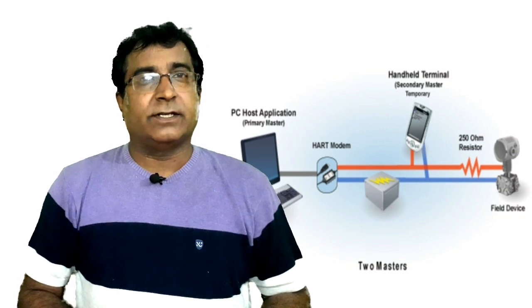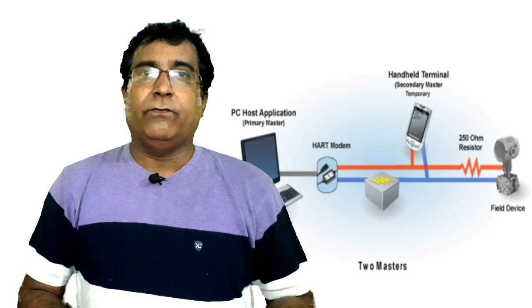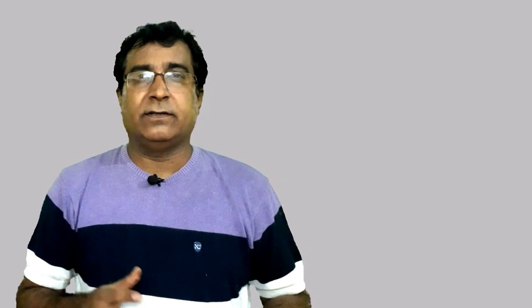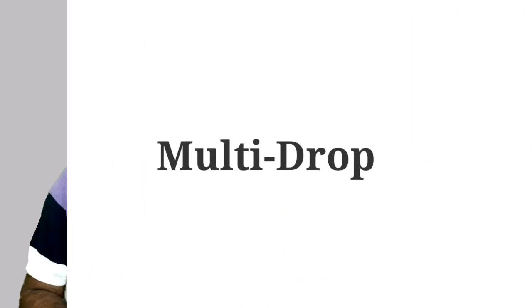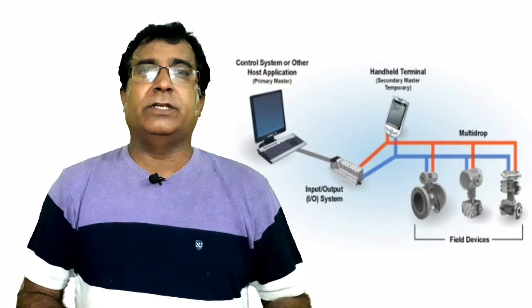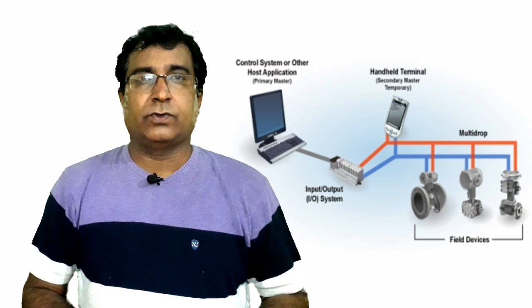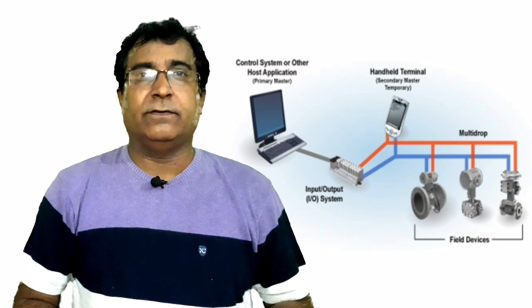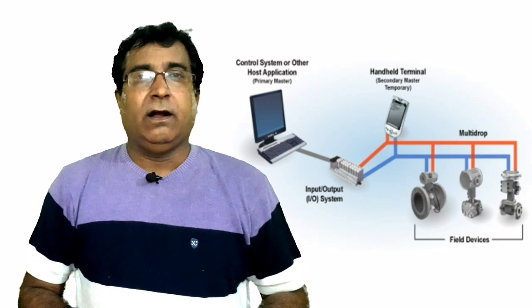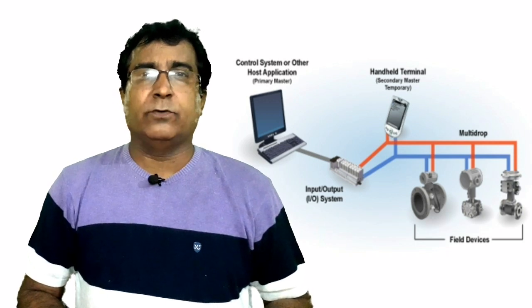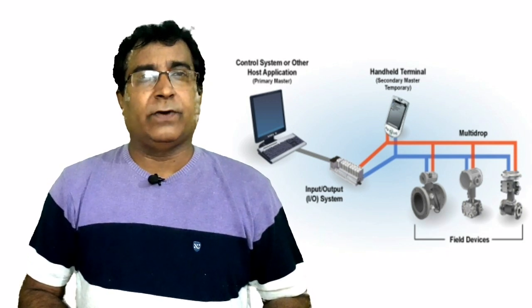This allows secondary masters such as a handheld communicator to be used without interfering with communication to and from the primary master, i.e., the control monitoring system. Now the second method is multi-drop connection. In multi-drop mode, the analog loop is kept fixed at 4 mA all the time, and all the transmitters are placed on a single cable connected with a host through a HART interface card which will be communicating with PLC and DCS. HART revision 3 allows polling addresses of the instrument in the range of 1 to 15, and HART revision 6 and 7 allow addresses from 1 to 63. Address 0 is allotted to the HHC or host.